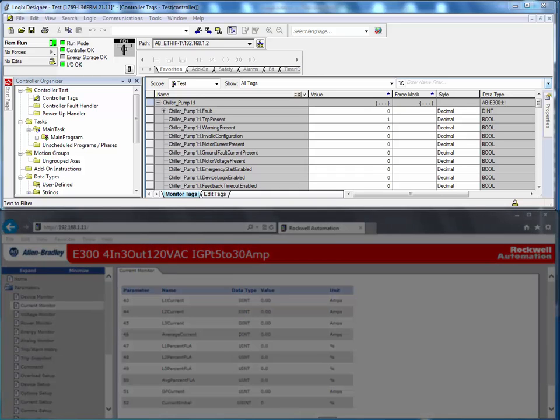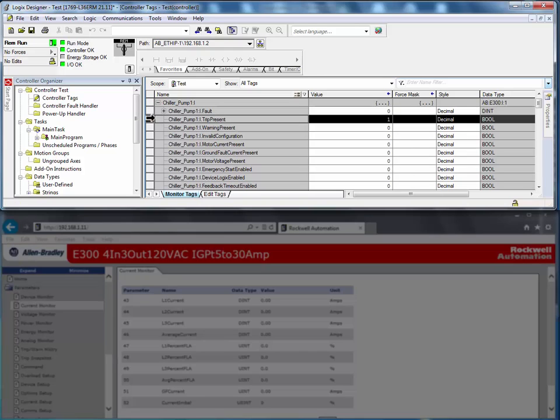In this example, the E300 Overload Relay had a trip event. We can see in the input tag diagnostics for input trip present indicates that the E300 is in a trip state.